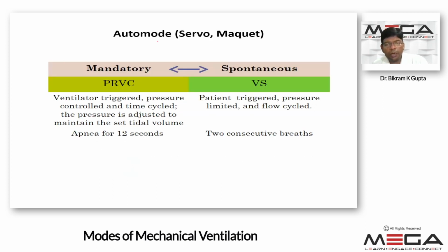What is this auto mode? This auto mode is actually a combination of PRVC and the volume support mode. So when the patient is in apnea for 12 seconds, the patient automatically goes into the PRVC mode, that is the ventilator triggered, pressure controlled, and time cycled mode. And if two consecutive spontaneous breaths are present, then the PRVC mode shifts back to the spontaneous mode, and that spontaneous mode is the volume support mode.